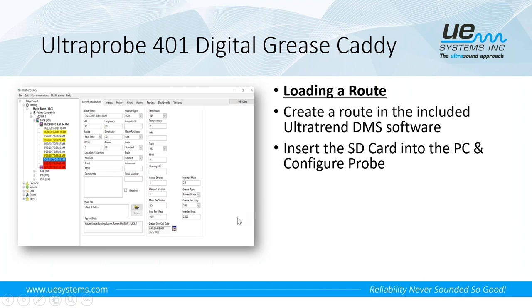Then we take the SD card, put it into our PC, and do configure probe. That configure probe step is a one-time step where you tell the software which UltraProbe we're using. This software works with five different UltraProbes, so it doesn't know which one you have until you tell it. We do configure probes, and it will look for what is connected. It'll recognize the SD card, and one of your options would be the UP401 on whatever drive or port you used. As long as you always use that same drive or port, you'll never have to do that step again.